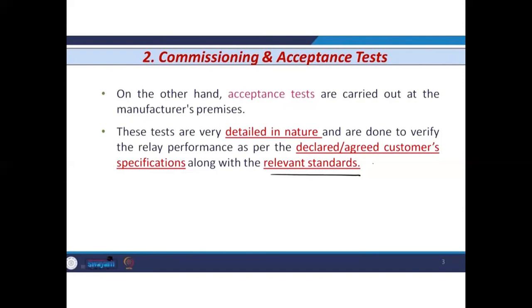These tests are carried out on the manufacturer's premises. They are very detailed in nature and are done to verify the relay performance as per the declared or agreed customer specifications, along with the relevant standards. As the name reveals, they check whether what the manufacturer is going to provide to the consumer is according to the customer's demand or not.